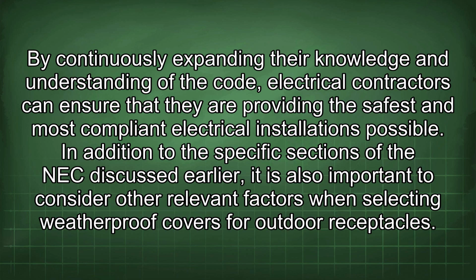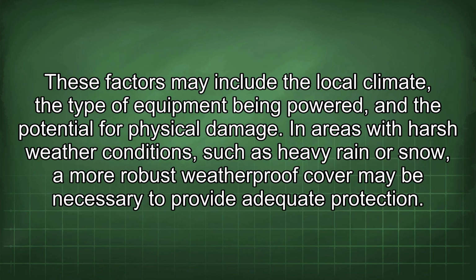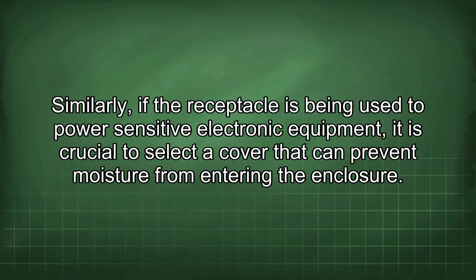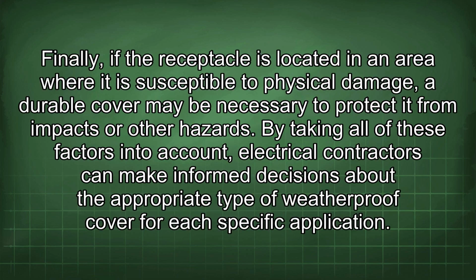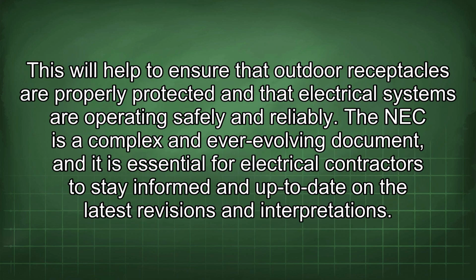In addition to the specific sections of the NEC discussed earlier, it is also important to consider other relevant factors when selecting weatherproof covers for outdoor receptacles. These factors may include the local climate, the type of equipment being powered, and the potential for physical damage. In areas with harsh weather conditions such as heavy rain or snow, a more robust weatherproof cover may be necessary to provide adequate protection. Similarly, if the receptacle is being used to power sensitive electronic equipment, it is crucial to select a cover that can prevent moisture from entering the enclosure. Finally, if the receptacle is located in an area where it is susceptible to physical damage, a durable cover may be necessary to protect it from impacts or other hazards. By taking all of these factors into account, electrical contractors can make informed decisions about the appropriate type of weatherproof cover for each specific application. This will help to ensure that outdoor receptacles are properly protected and that electrical systems are operating safely and reliably.